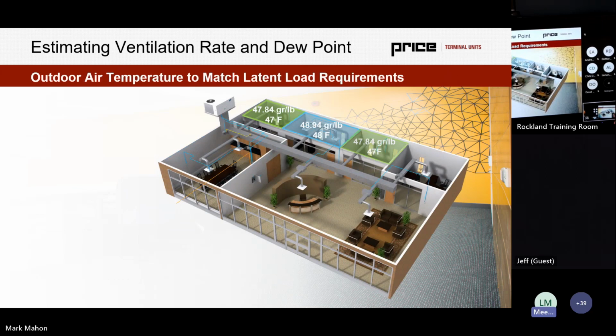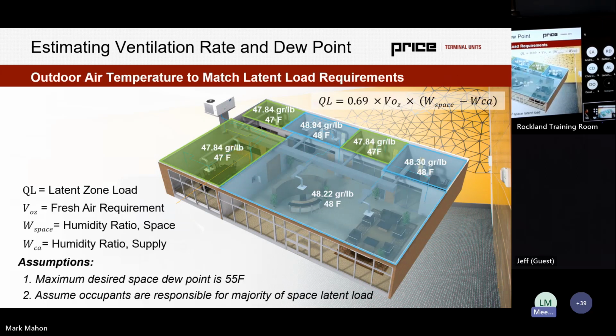And what we want to do is try to meet that with only the ventilation air requirement. And this equation here on screen, QL equals 0.69 times the ventilation rate times the difference between the humidity ratio of the space and the supply air, is what allows us to calculate this out. And so what ends up happening when we go through these kinds of examples in this exercise with an office environment is that it's going to end up needing us to cool the air further on design day than the 55 you'd typically see in an all-air system.